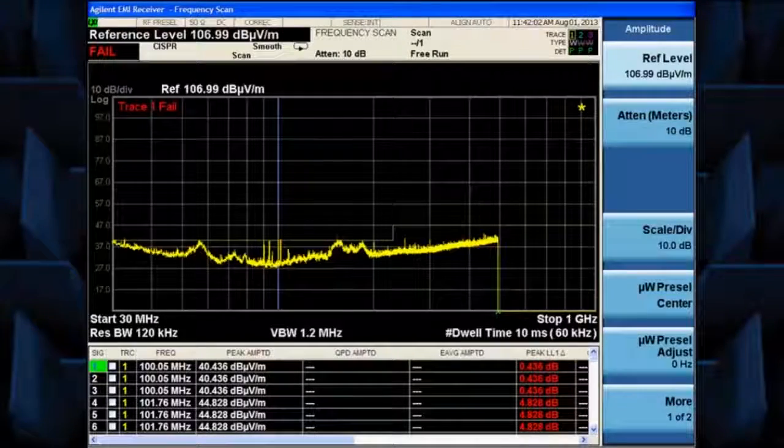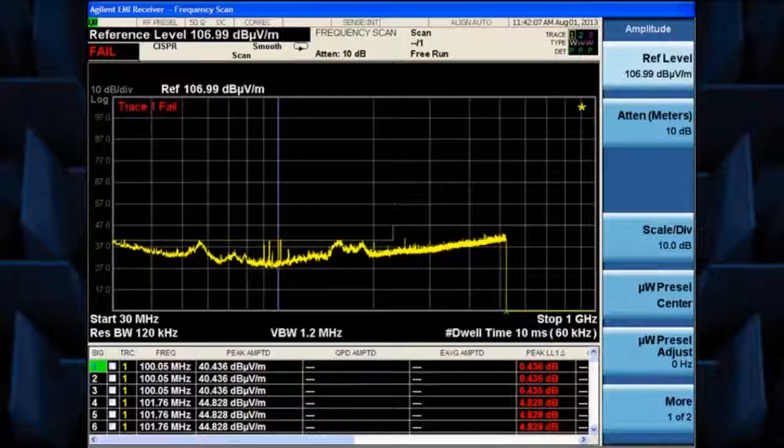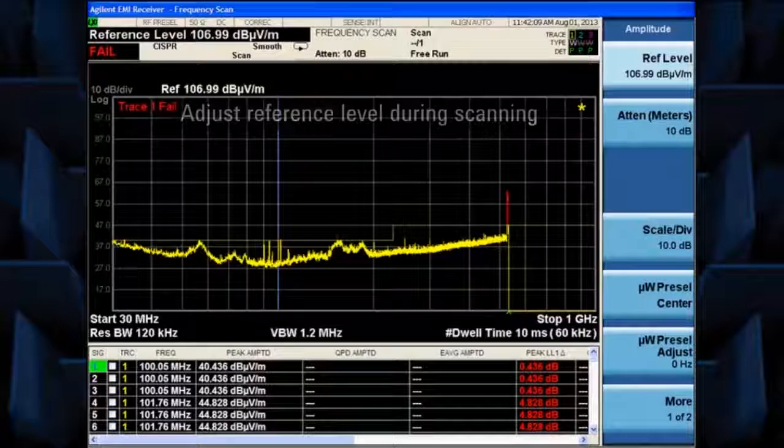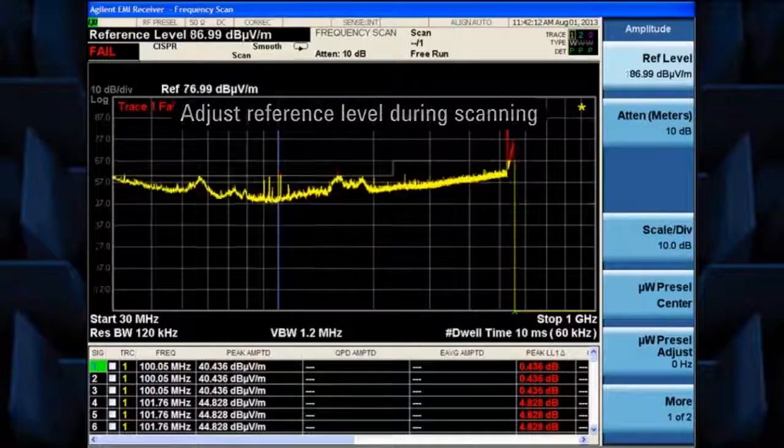To help speed testing, the MXE provides access to key menus during a scan. For example, you can adjust the reference level or measure with a marker if needed while scanning is in progress.